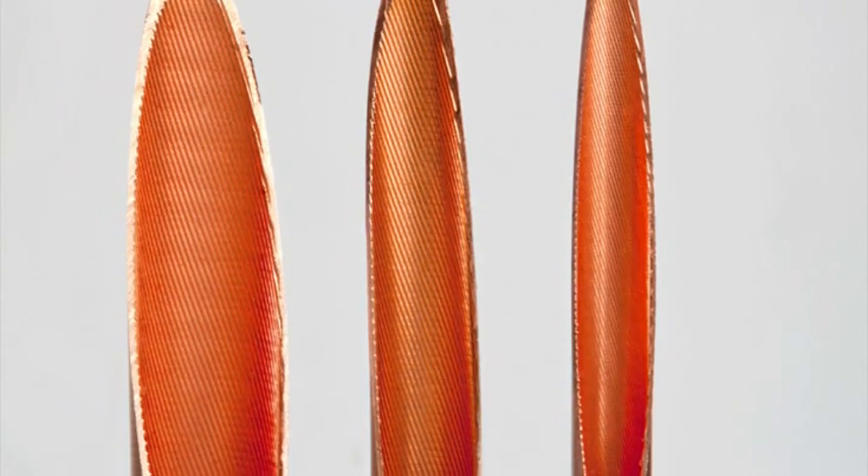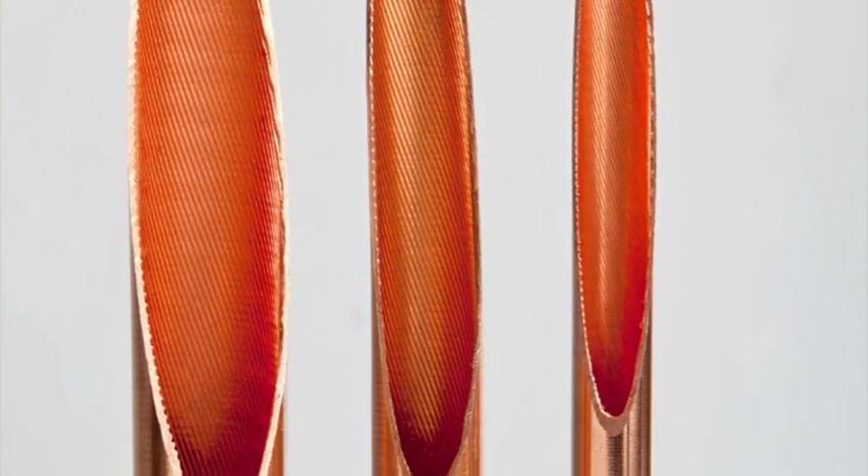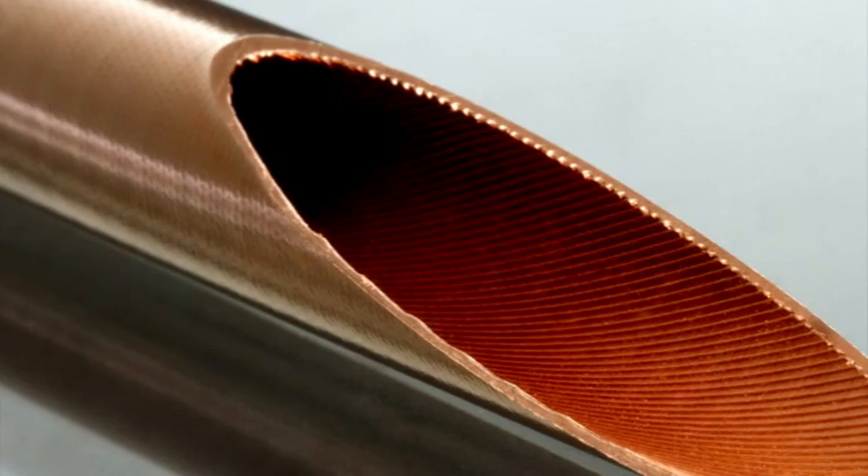This tube can, with internal screws, optimize the heat exchange by 15% to 40%, compared to smooth tubes. The Eluma Groove tubes are extruded. You take a base tube, after it passes through the process of extrusion and wire-drawing, you put an internal tool in the tube and, by itself, through the process of rotation, it grooves the internal tube. These internal grooves, with refrigerant fluid flowing through them, will create turbulence and generate better thermal exchange in the application.